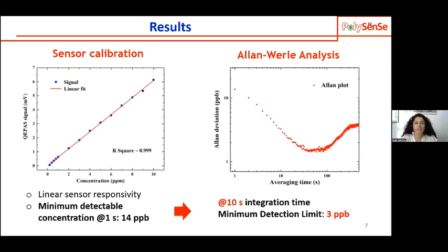The minimum detection limit can also be improved, so lowered, by increasing the lock-in integration time. For example, by performing an Allan deviation analysis, we verified that using a lock-in integration time of 10 seconds, the minimum detection concentration can be lowered down to 3 ppb.